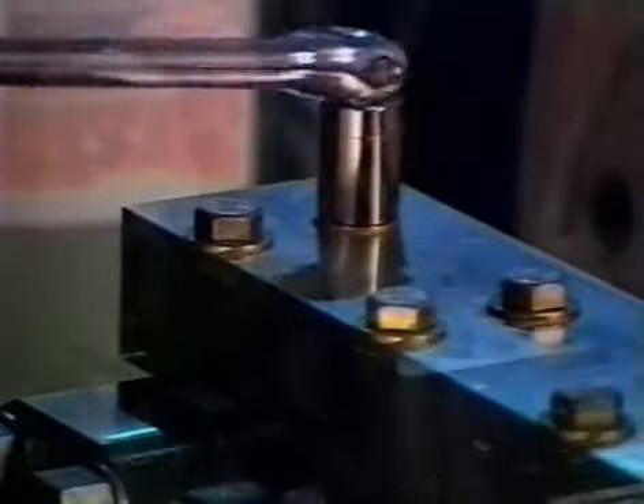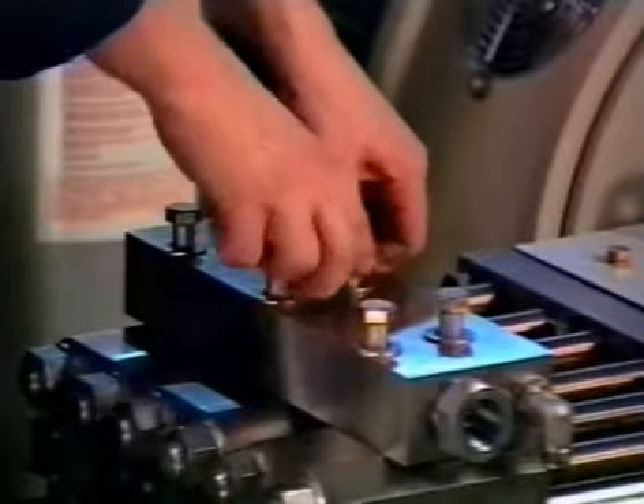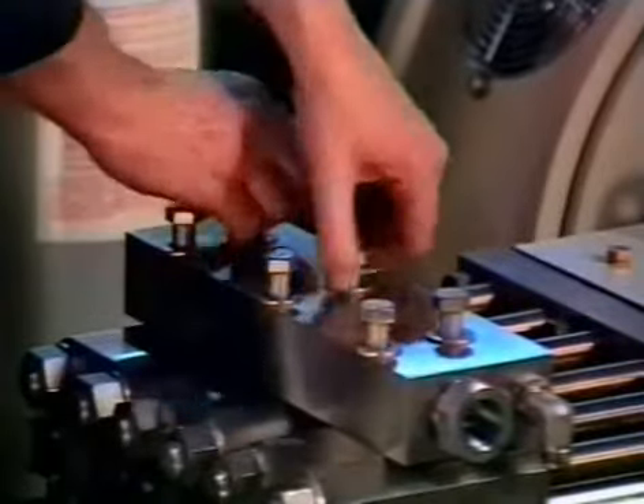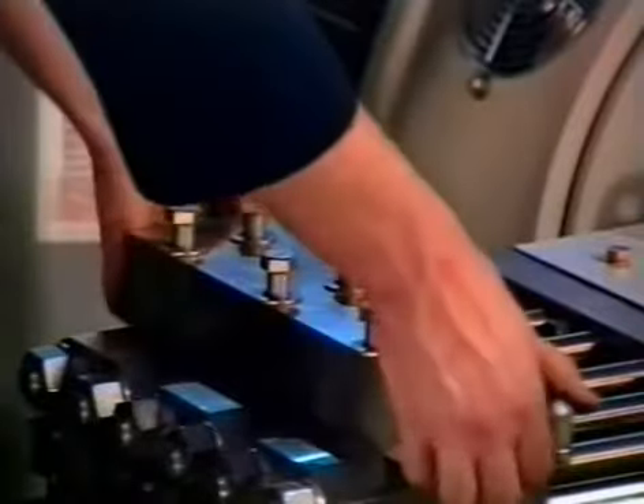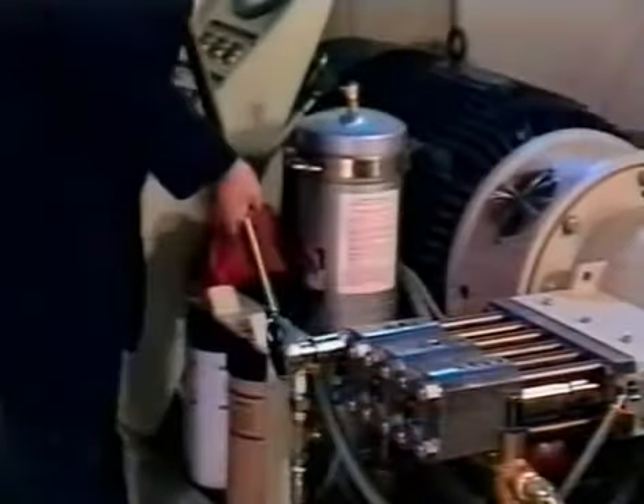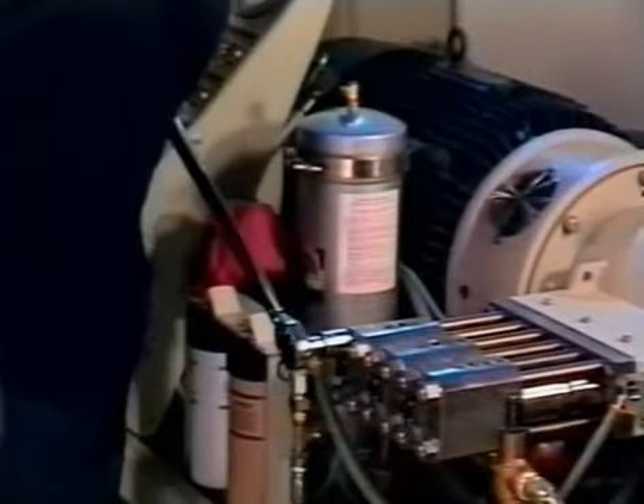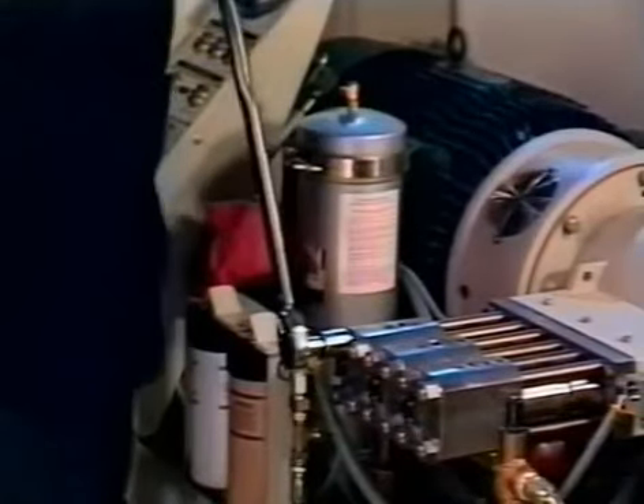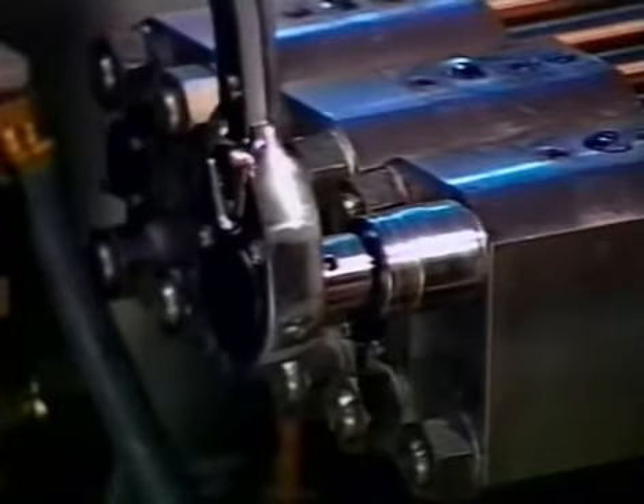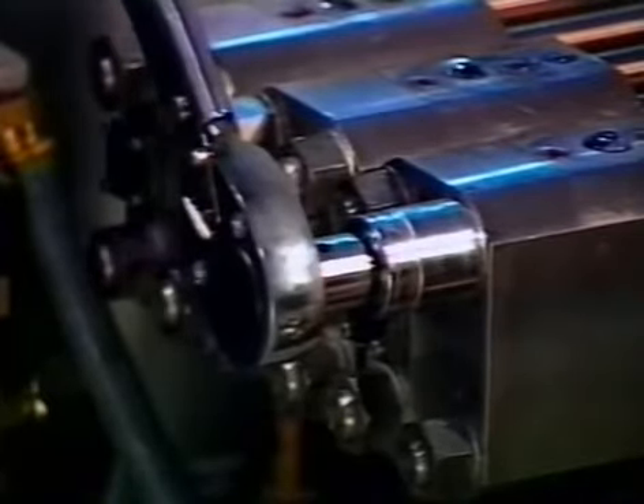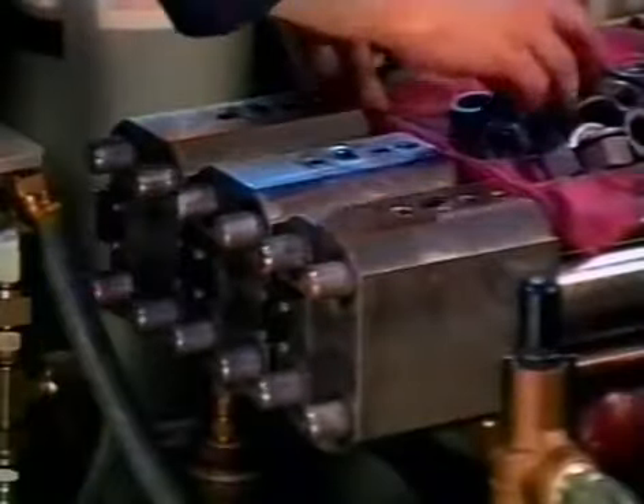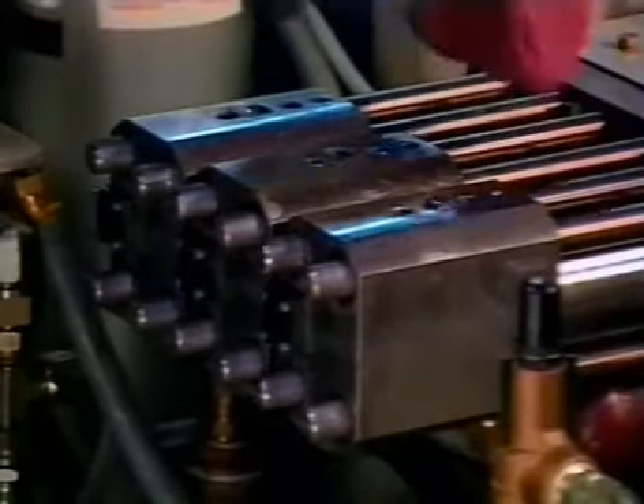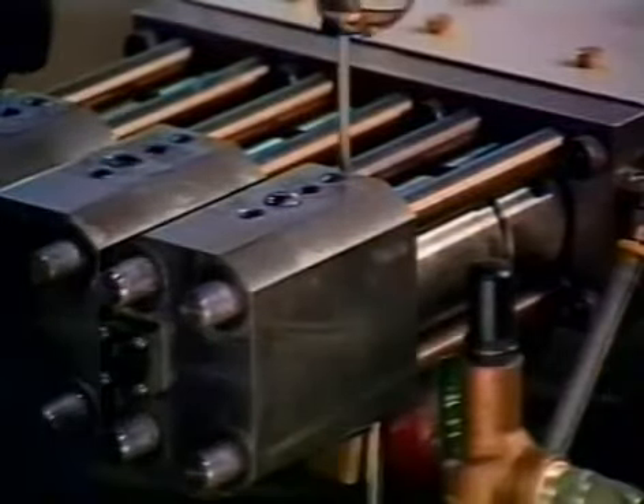To avoid damaging the O-rings and backup rings that create a seal between the end caps and manifold, lift the manifold straight up. Do not slide the manifold on top of the end caps. Next, remove the 12 tie rod nuts. Now, using 2 screwdrivers or pry bars, pry the end caps from the high-pressure cylinders.